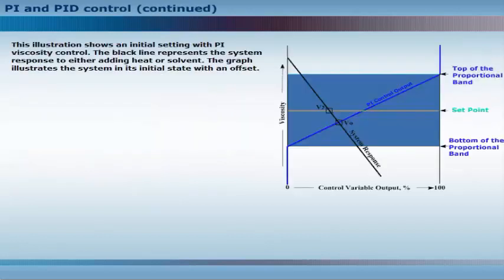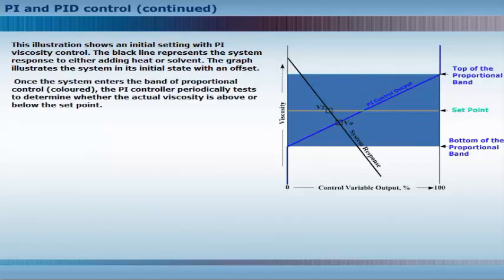This illustration shows an initial setting with PI viscosity control. The black line represents the system response to either adding heat or solvent. The graph illustrates the system in its initial state with an offset. Once the system enters the band of proportional control, the PI controller periodically tests to determine whether the actual viscosity is above or below the set point.